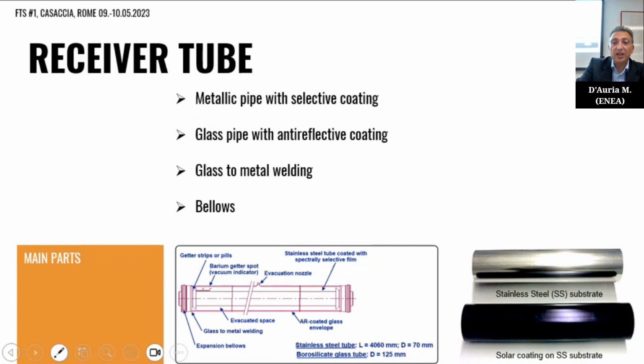So the heat transfer fluid flows through the metallic pipe to collect thermal energy absorbed by the selective absorber. The metallic pipe needs to fulfill several requirements: good thermal conductivity to transfer the heat collected by the selective absorber, good mechanical properties to withstand high temperature and operation pressures, and good corrosion resistance regarding the heat transfer fluid employed in the system. Hence, AISI 321 stainless steel is commonly used in molten salt receiver tubes.